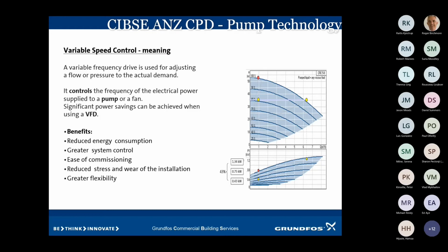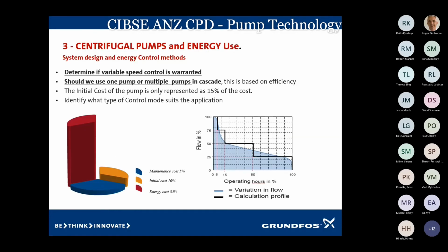And we know that when we're running a pump on a system, unless it's a cooling tower or a fixed duty, generally we only run that pump for a very, very short time on the peak load. If I just take you back, you can see here how the system might be working. So at the peak load, for a very, very short time, but most of the time your hours are sitting spread down on low loads, and this is where the VSD and the energy savings can be huge.